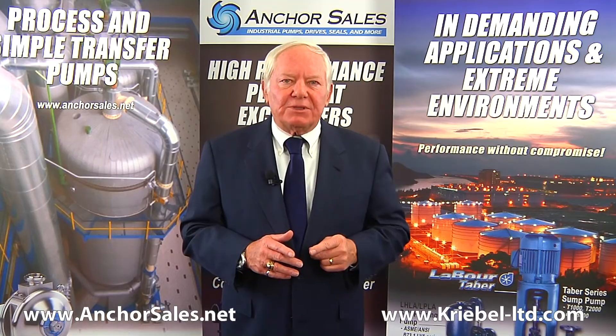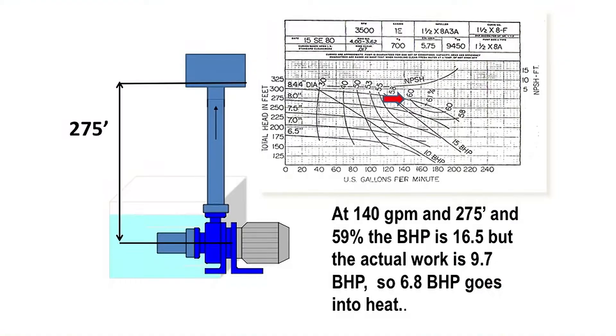This is easy to explain. Looking at a system, you can see that the power consumed by the pump is greater than the actual — called theoretical — power developed by the pump flow and head, because it is not 100% efficient. So where does that difference go? Into heat.